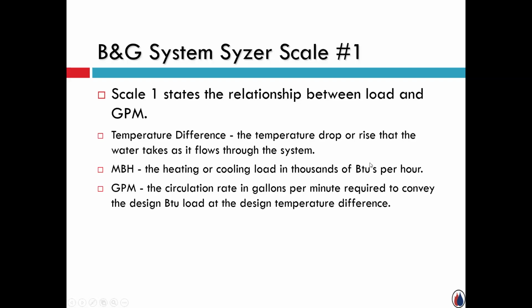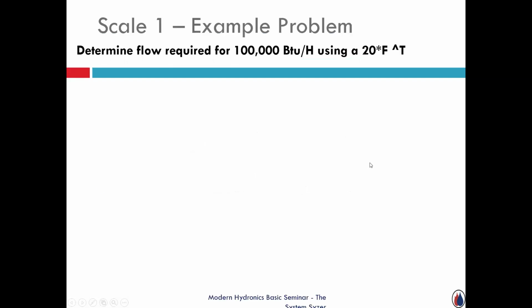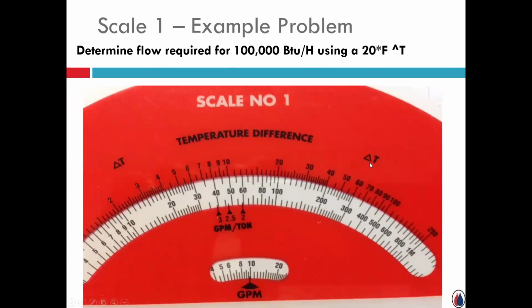So, temperature difference, load, either heating or cooling load in thousands of BTUs, and then again GPM, circulation rate in gallons per minute. Just real quick, easy numbers, very low, probably not what you're typically designing around: determine the flow rate required for 100,000 BTUs an hour at a 20 degree delta T.